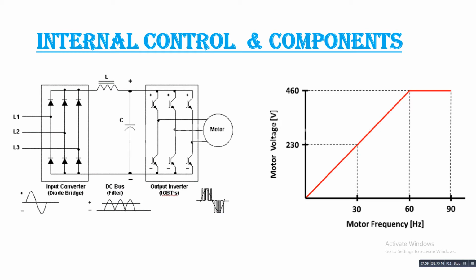Okay, and you can see the graphs also, outputs. The motor frequency and motor voltage are directly proportional. So whenever the frequency increases, the motor voltage also increases till the rated voltage. Usually you can set your motor frequency and motor voltage in VFDs. Accordingly, this will control from zero minimum to maximum frequency and voltage.